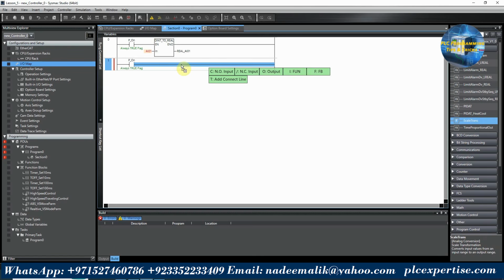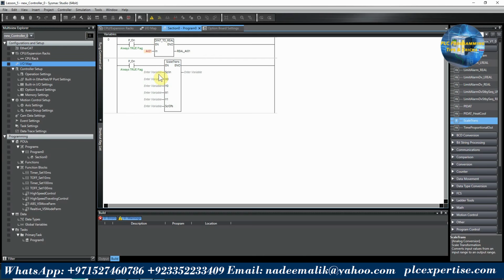We will drag and drop it here, and as you can see, it has a few inputs. We will discuss all these inputs step by step. First of all, we have scale in, and here we have to put this real analog channel value. We will paste here this raw value coming at channel 1. Next, we have the X0. X0 is the minimum raw value.